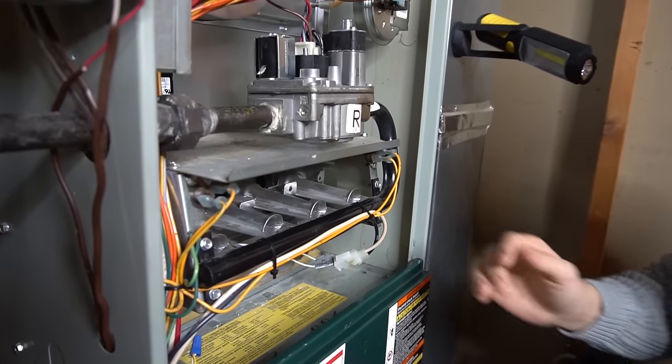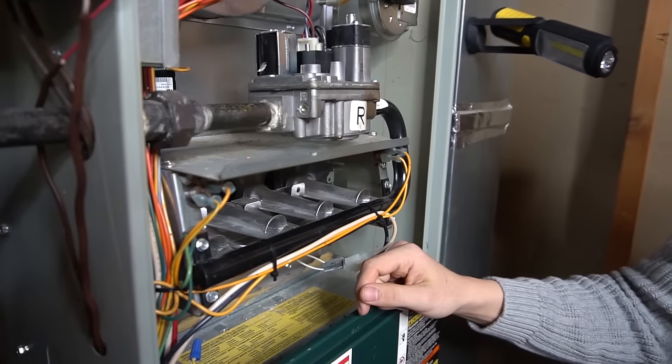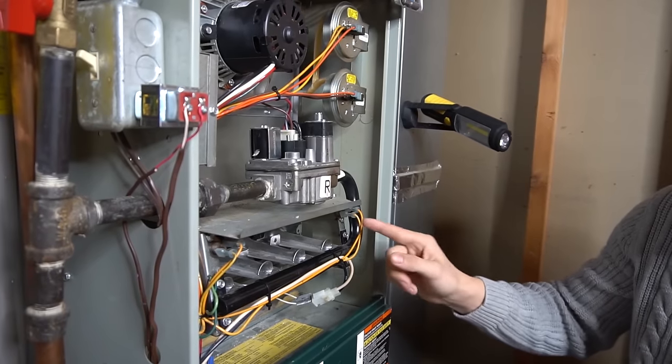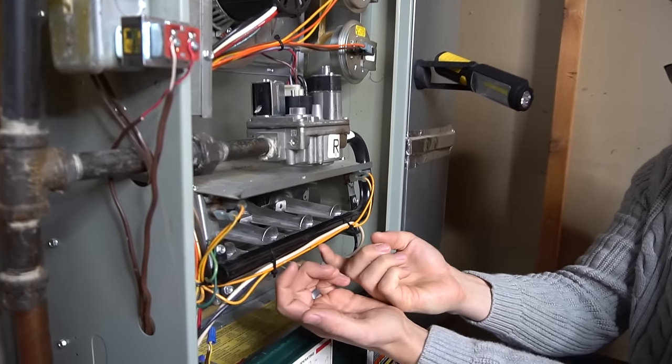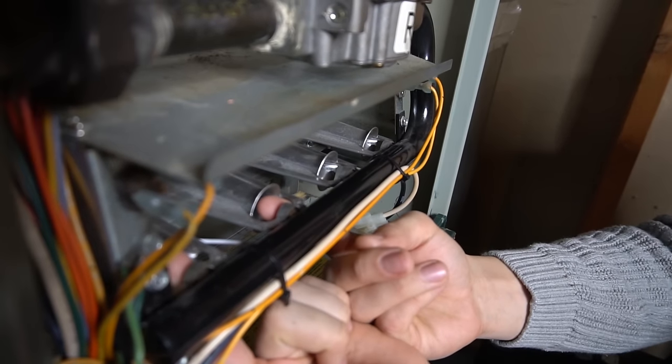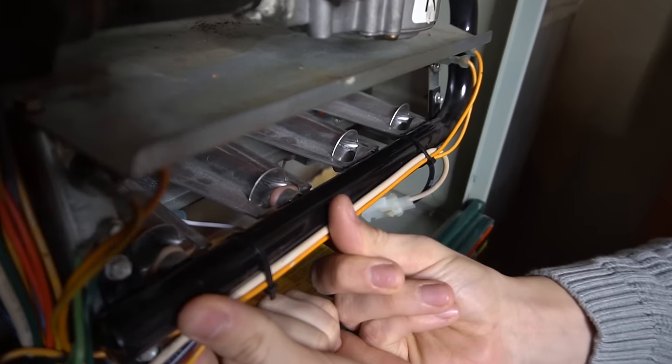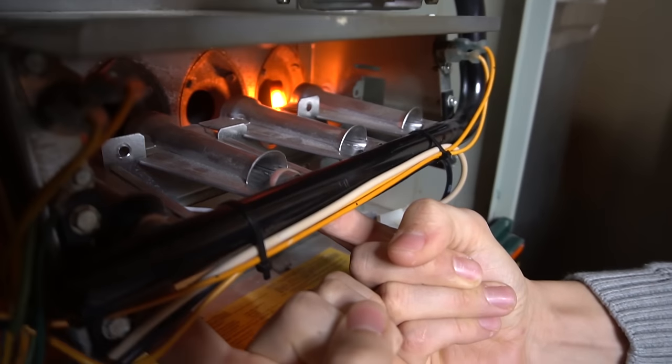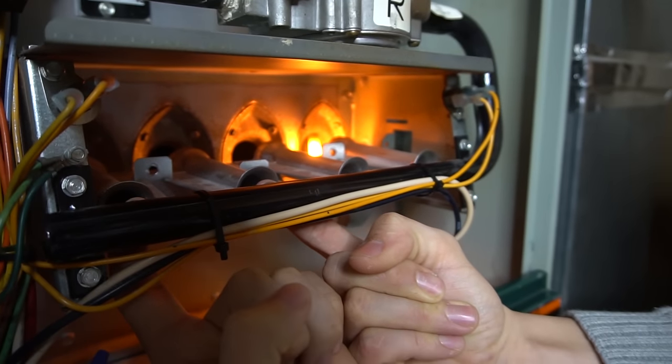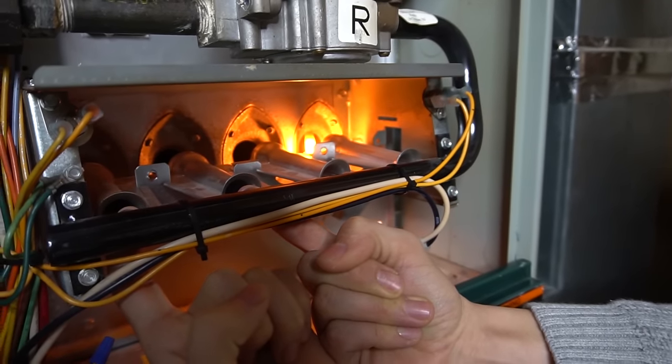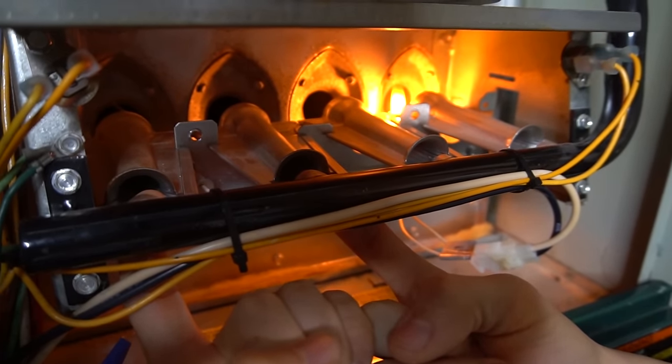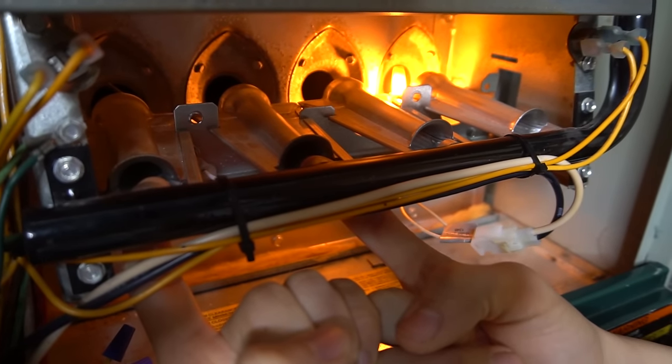So I turn my furnace back on, and there goes my inducer motor. Pressure switch is closed. My igniter should start to glow. And for example, I'm going to go ahead and just plug these two orifices with my fingers, just to show you what that would look like. So if this is what you're seeing, only two burners come on, or one or three, that would mean that your gas orifice, or a couple of them, are plugged up.